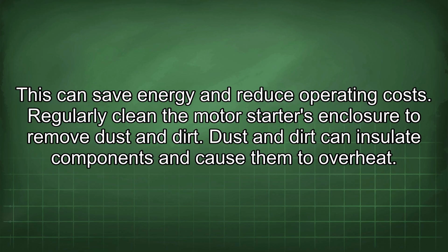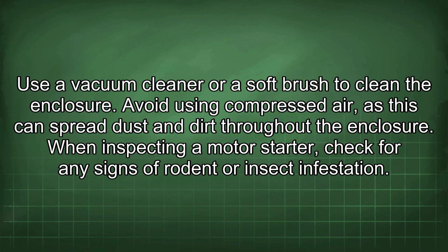Regularly clean the motor starter's enclosure to remove dust and dirt. Dust and dirt can insulate components and cause them to overheat. Use a vacuum cleaner or a soft brush to clean the enclosure. Avoid using compressed air, as this can spread dust and dirt throughout the enclosure.